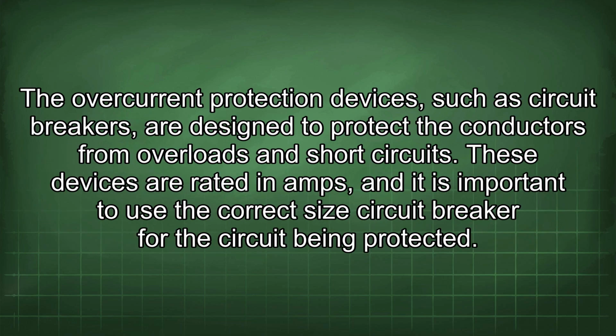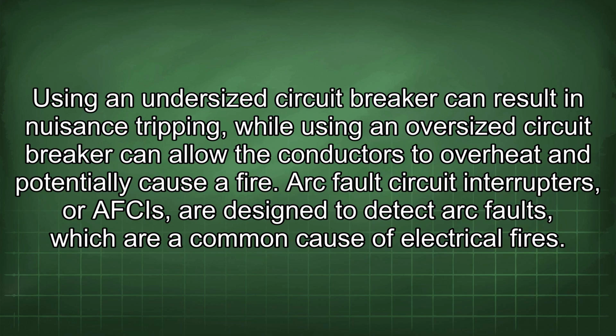The overcurrent protection devices, such as circuit breakers, are designed to protect the conductors from overloads and short circuits. These devices are rated in amps, and it is important to use the correct size circuit breaker for the circuit being protected. Using an undersized circuit breaker can result in nuisance tripping, while using an oversized circuit breaker can allow the conductors to overheat and potentially cause a fire.